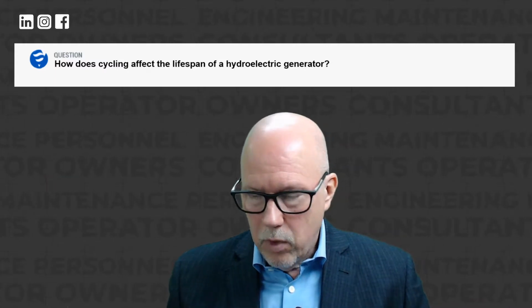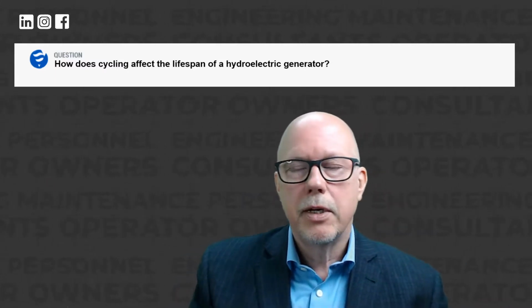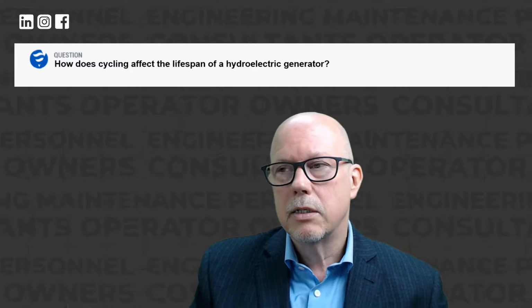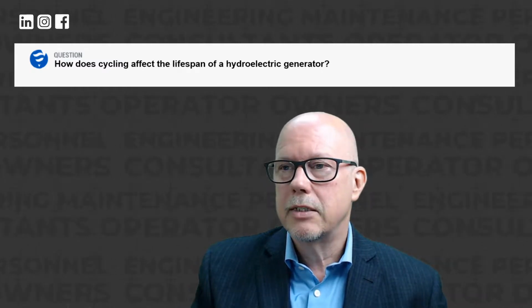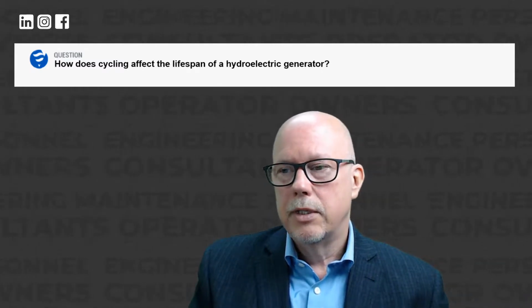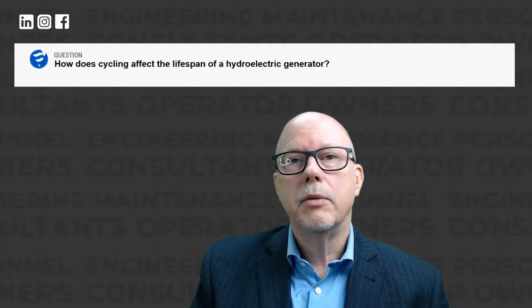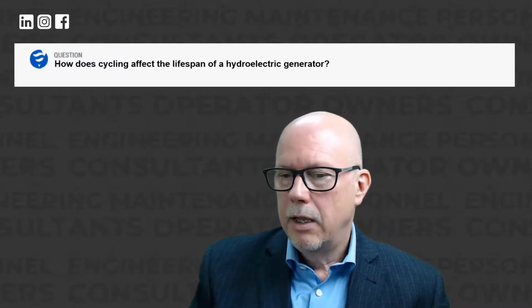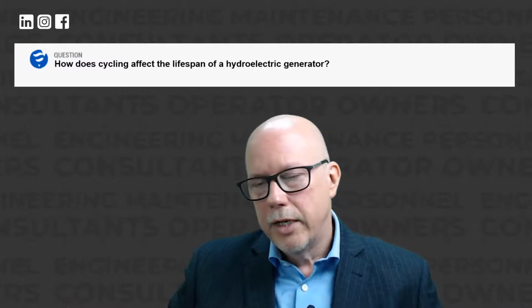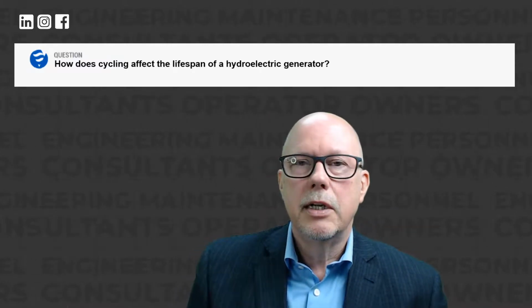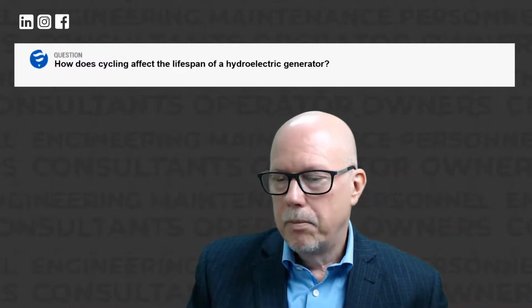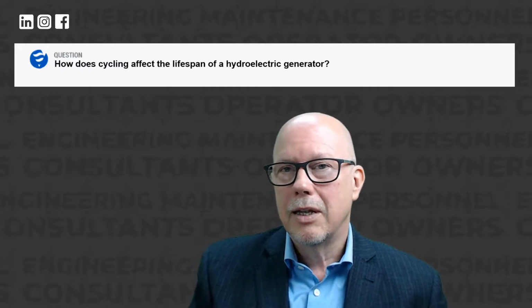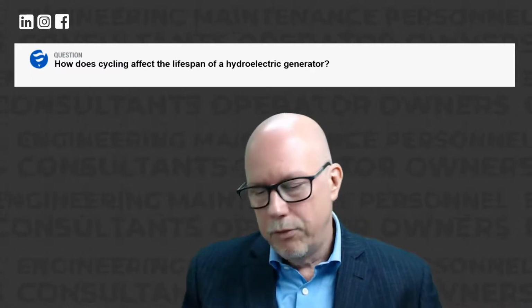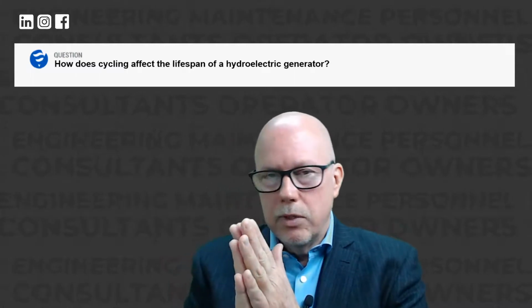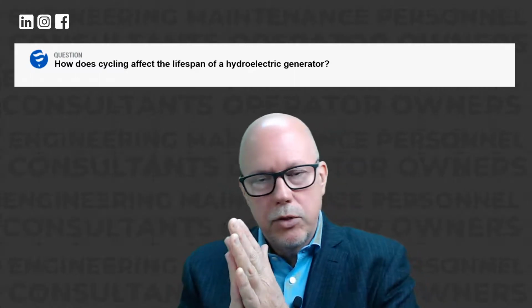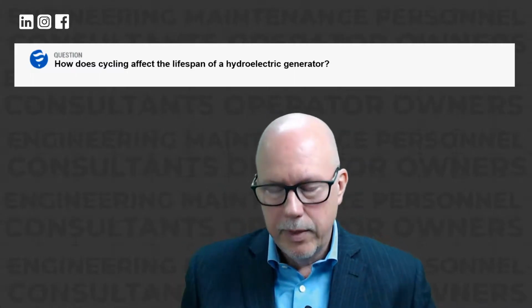Windings, or epoxy mica insulation, have tremendous electrical properties—fantastic dielectric—but horrible mechanical properties. It's basically glass, and if you've shaken a mirror or a window, you can see it can crack. Plus glass does not like to rub, so if you expand and contract, you get this rubbing action. If you do it frequently, you'll deteriorate the insulation.